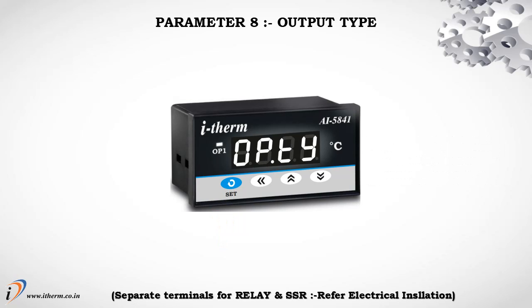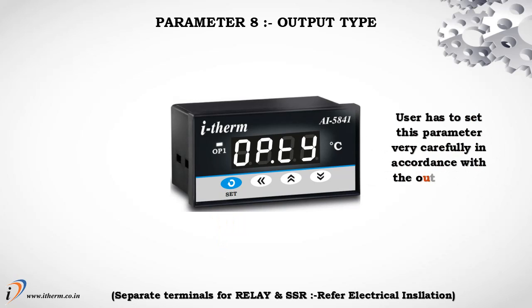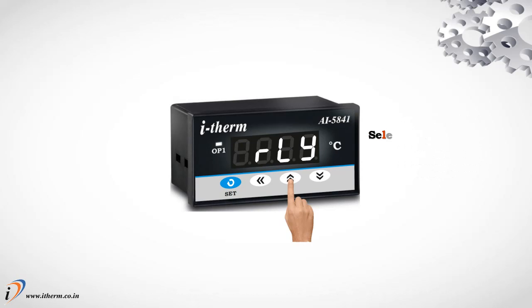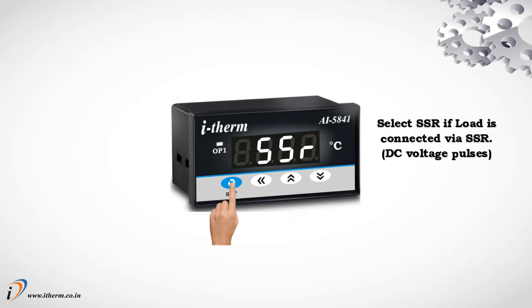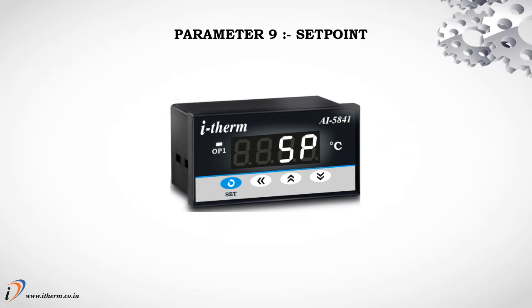Parameter 8: Output Type. The user has to set this parameter very carefully in accordance with the output used. Select Relay if the load is connected via contactor. Select SSR if the load is connected via SSR.